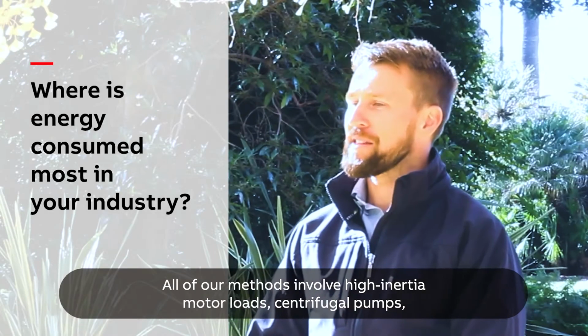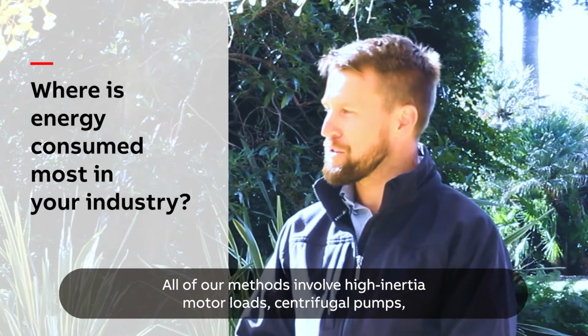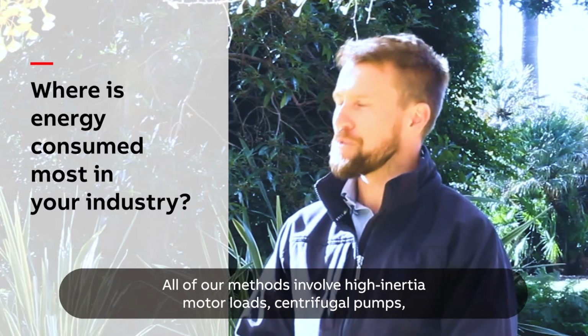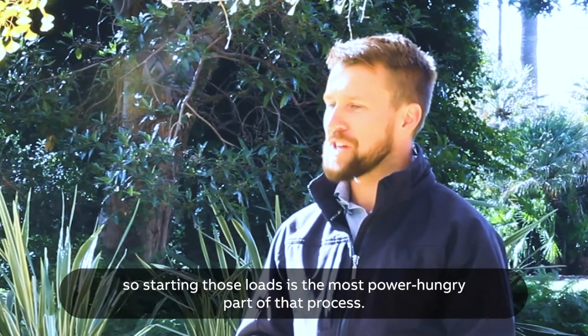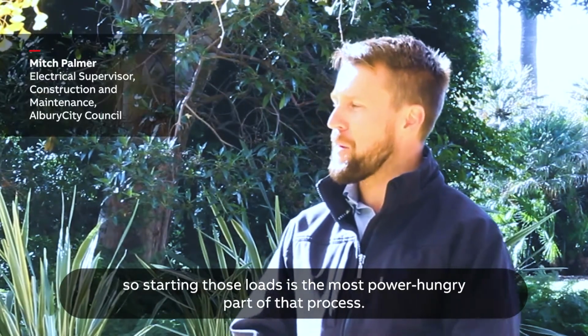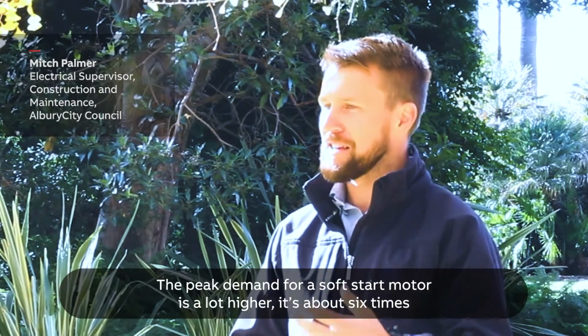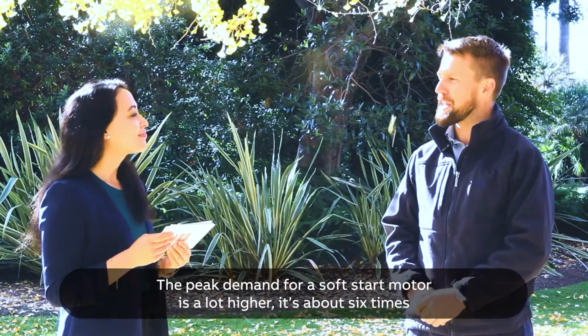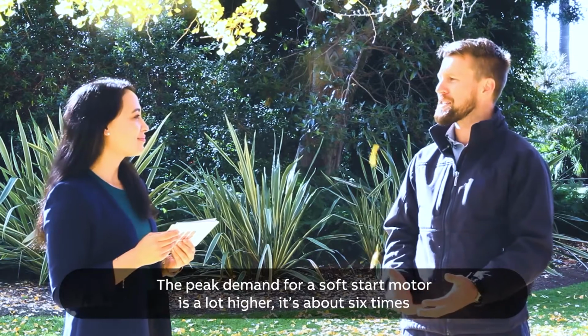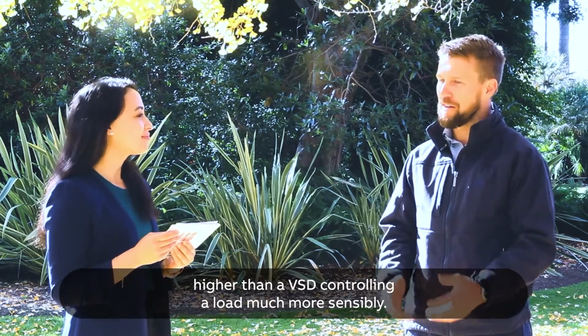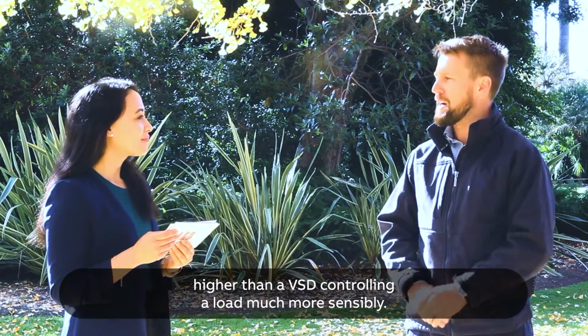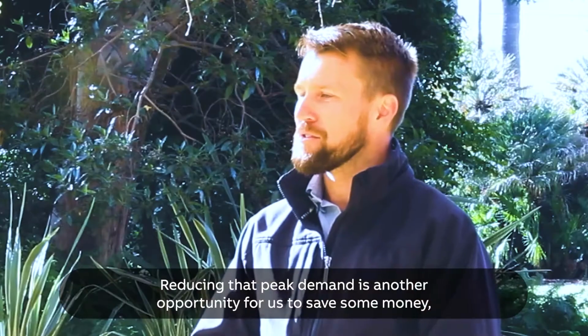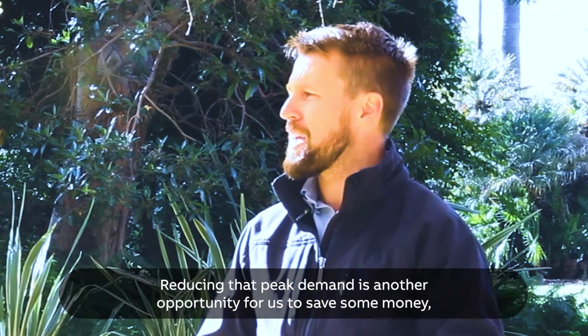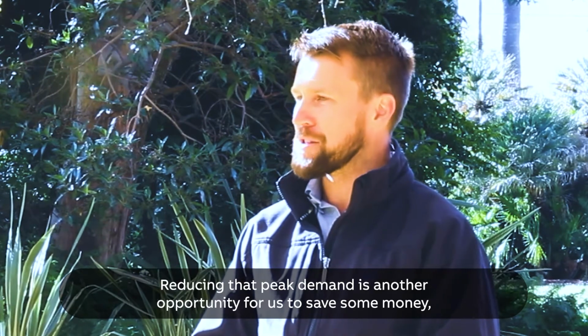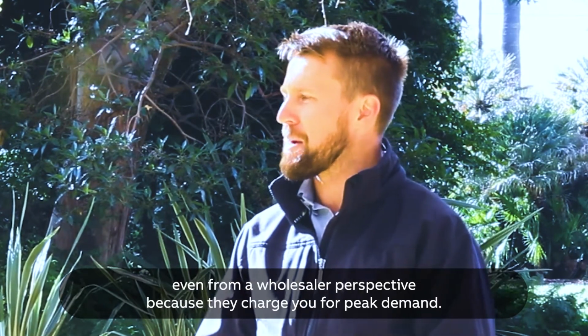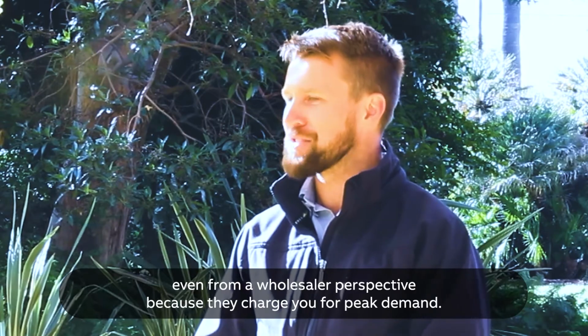Yeah, all of our methods involve high inertia motor loads, centrifugal pumps, so starting those loads is the most power hungry part of that process. The peak demand for a soft start or a DOL start motor, for example, is a lot higher. It's about 6 times the starting current of what a VSD can do when it's controlling a load a lot more sensibly. So yeah, just reducing that kVA, that peak demand, is another little opportunity for us to save some money, even from a wholesaler perspective, because they charge you for peak demand.